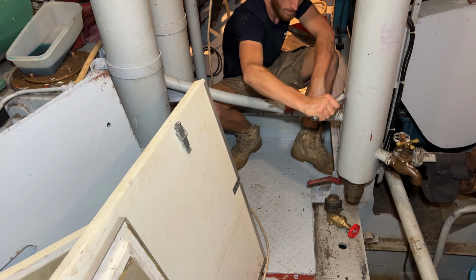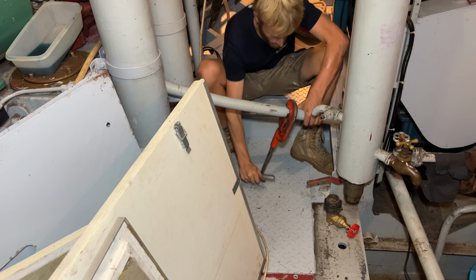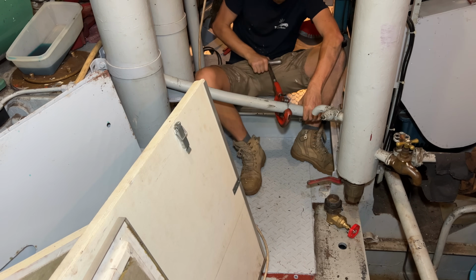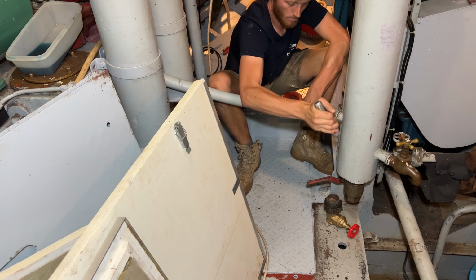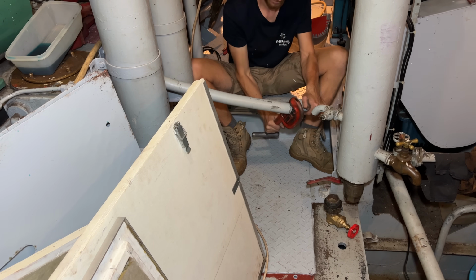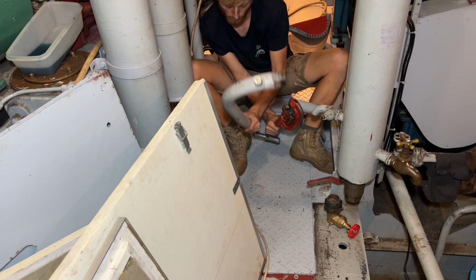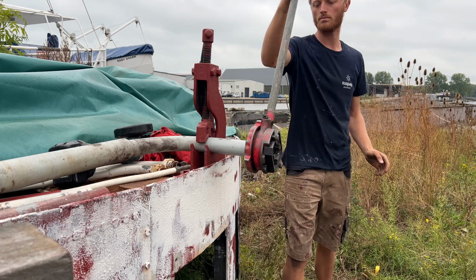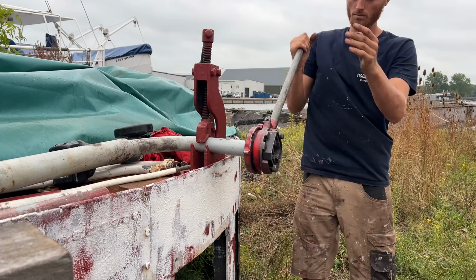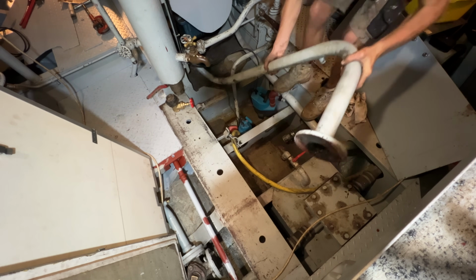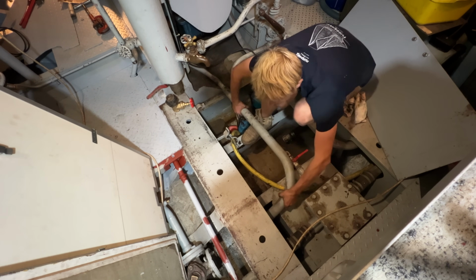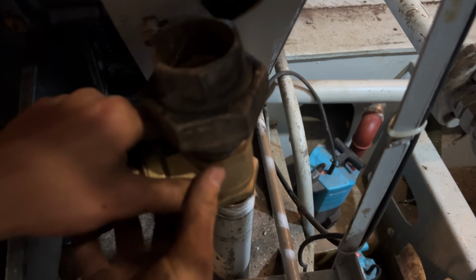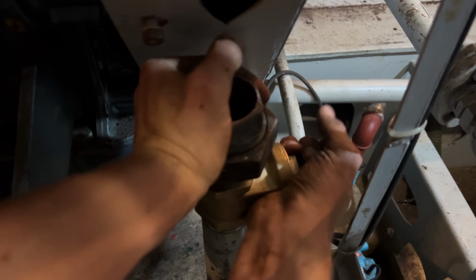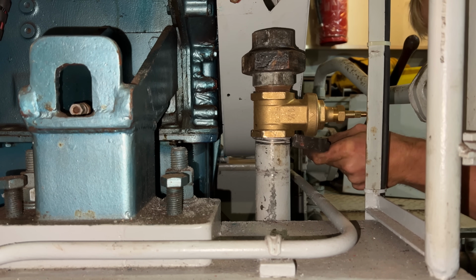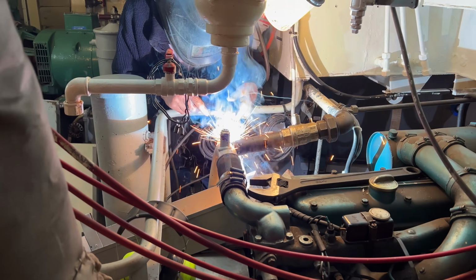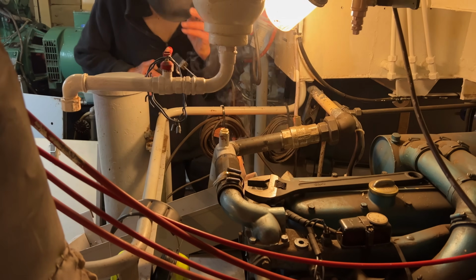To keep the mess to a minimum, I'm using a manual pipe cutter instead of an angle grinder. I had to cut the pipe anyways to install the throttle valve here as well. In this line it's more important, because not all the main engine's coolant can flow through the coil in the buffer tank. With the valve, we can allow a certain amount to flow straight to the keel coolers. The branch on the top half of the pipe has to be tack welded on location and can be finished outside.